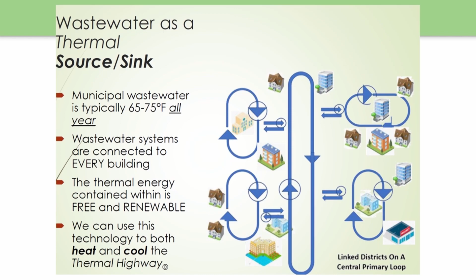40% of the load is not unusual for us to see downtown in a Manhattan high-rise building. The water and wastewater could provide up to 40% of the ultimate loading, as long as I have thermal storage to take advantage of the flow times. That's the key portion.